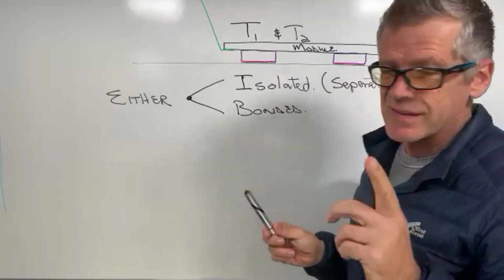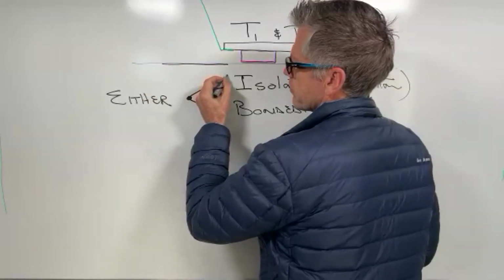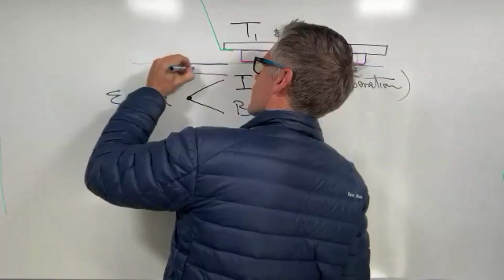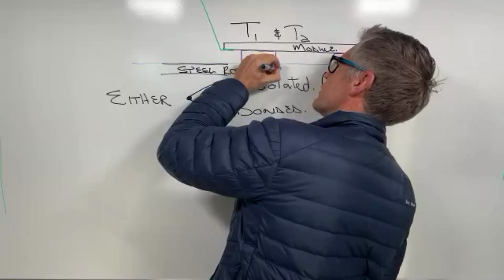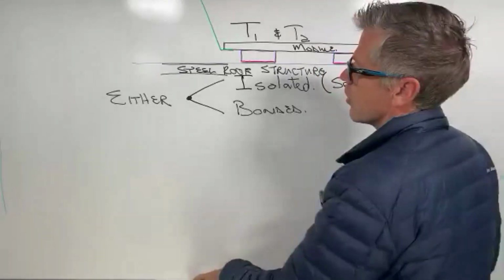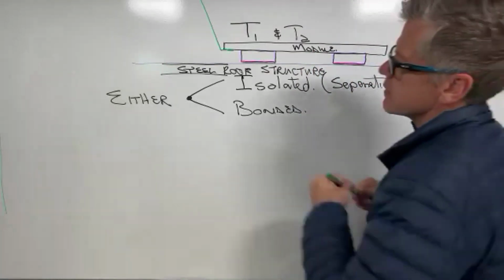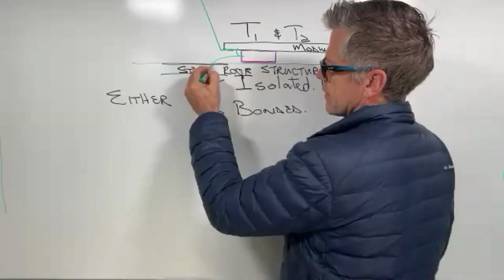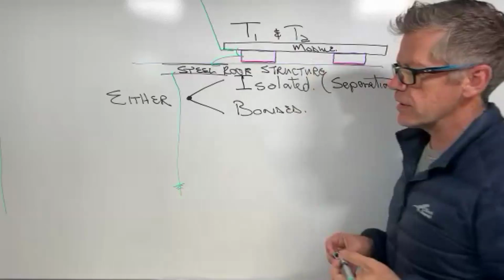But now what that means is that between the roof, so if I have my purlins, what do we call this, steel structure? I have my steel roof structure over there. This is now going to mean that you are going to have to ensure that that is continuous to that, is continuous to that, is continuous to whatever it is.